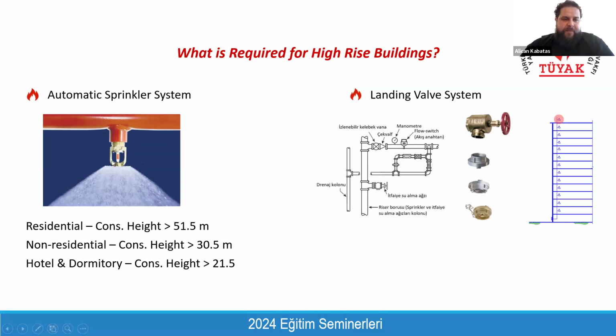When we look at the automatic sprinkler system that you see on the left hand side of the slide, this is automatic suppression system. You can see in many of the high-rise building and shopping malls and any other assembly buildings such as theaters. It is becoming mandatory for residential buildings if the construction height exceeds 51.5 meter. And for non-residential buildings, the limitation is 30.5 meter. But for the hotel and dormitories, it means where the people are sleeping, the limitation is much less than the other buildings. It is only 21.5 meters. It means if you are designing hotel, dormitory, or any kind of sleeping building, you should pay attention to the requirements of the automatic sprinkler system.